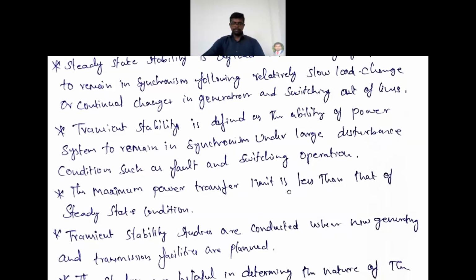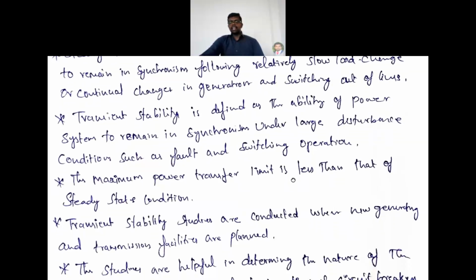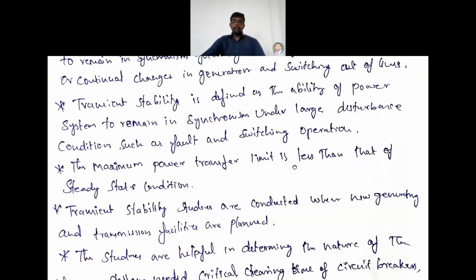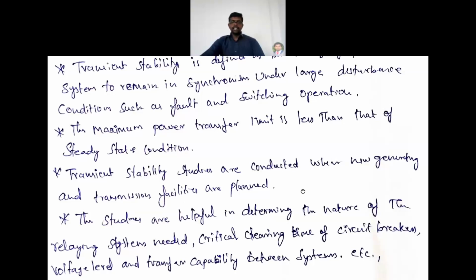The maximum power transfer limit is less than that of the steady state condition. Transient stability studies are conducted when new generating and transmission facilities are planned. These studies help determine the nature of the relaying system and the critical clearing time of the circuit breaker, which you already studied in protection - this study helps identify that critical clearing time in advance.